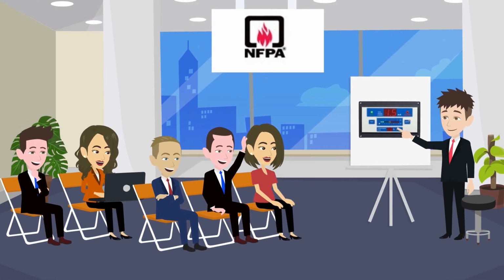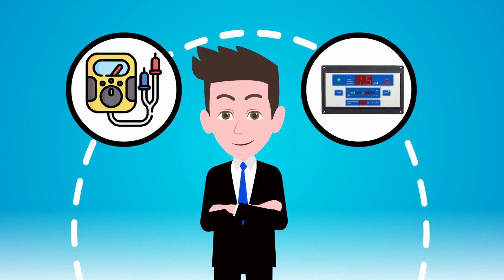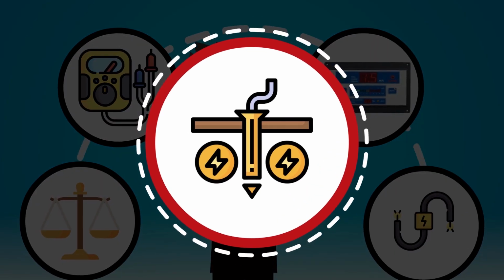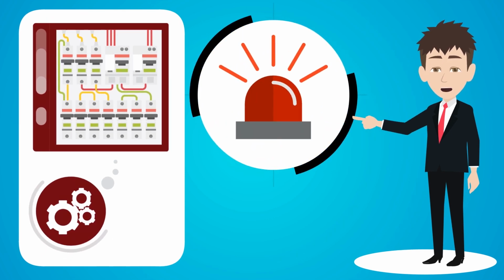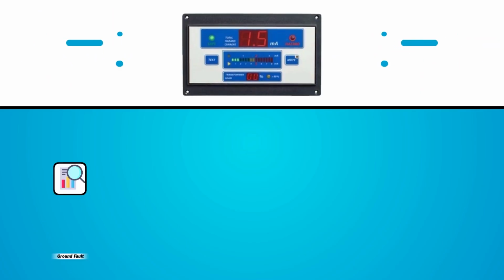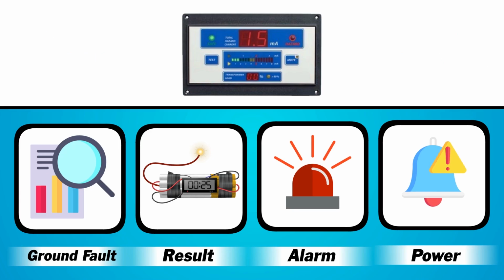Section 3.3.9 of NFPA 99 defines a line isolation monitor as a test instrument designed to continually check the balanced and unbalanced impedance from each line of an isolated circuit to ground and equipped with a built-in test circuit to exercise the alarm without adding to the leakage current hazard. In an isolated power circuit, a ground fault would result in an alarm, but power would not be interrupted.